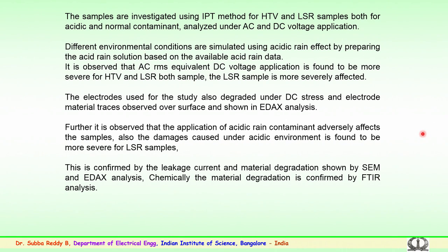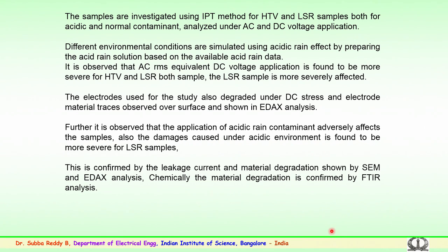Electrode material traces were observed left over on the surface, as confirmed by energy dispersive X-ray (EDAX) analysis. It was also observed that the application of acid rain contaminant adversely affects the samples, and the damage under acidic environment is found to be much more severe for the liquid silicon rubber samples. This is confirmed by the leakage current measured continuously during experimentation, and by surface analysis using SEM and EDAX. Chemically, the material degradation is confirmed by Fourier transform infrared (FTIR) analysis.